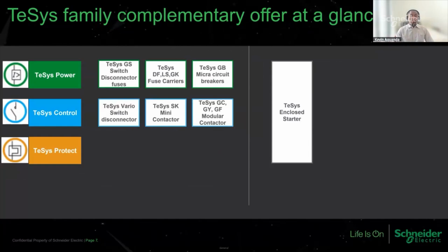Within the range, we do have some other complementary offers as well. So we have elements such as switch disconnectors, so the TeSys Vario range, the TeSys GS switch disconnector fuses, modular contactors, fuse carriers, to give under the TeSys umbrella the full set of requirements for motor management and control. And we have as well the enclosed starters that have our components packaged within an enclosure for all-in-one solution for direct online starters, reversers, and so on.